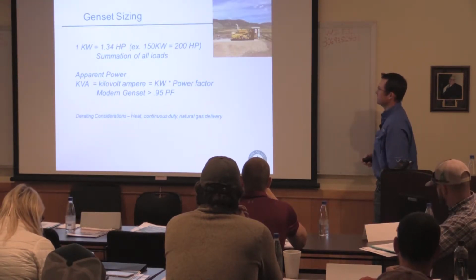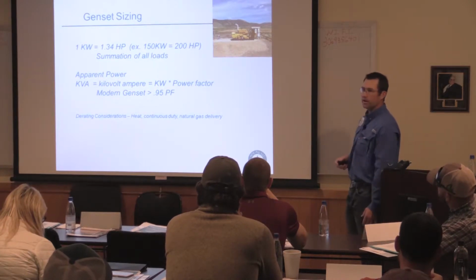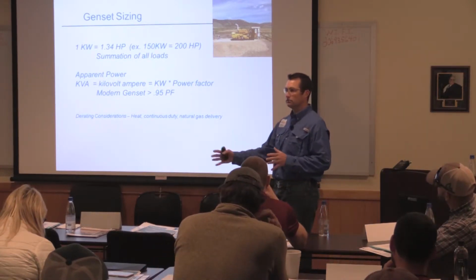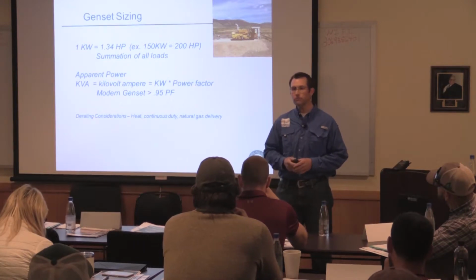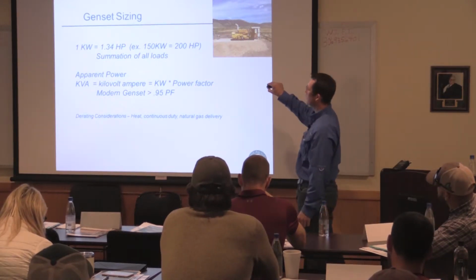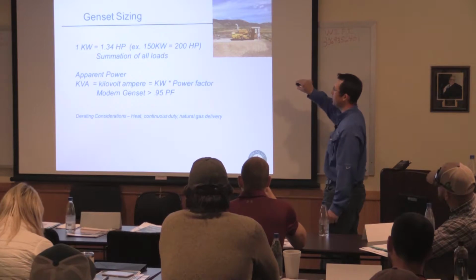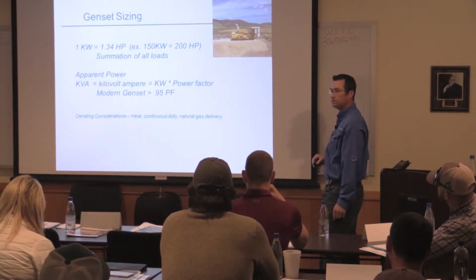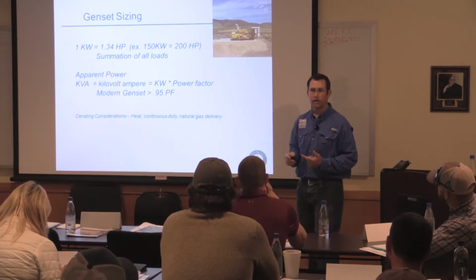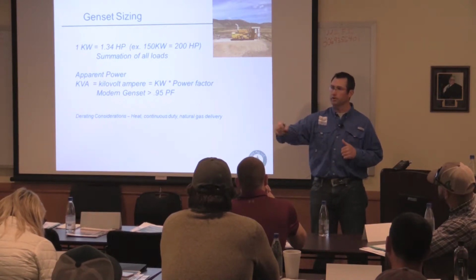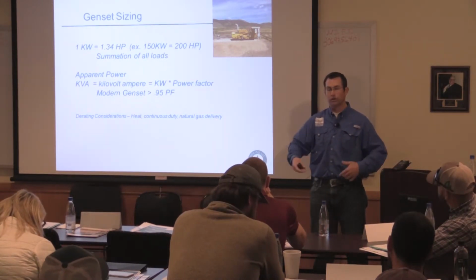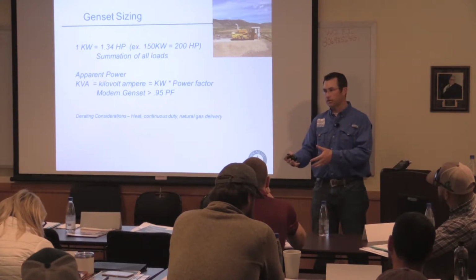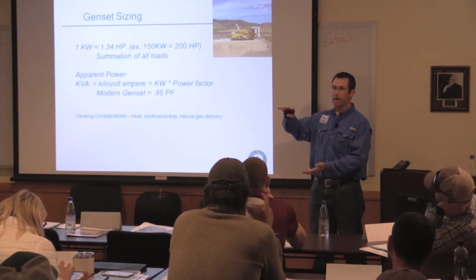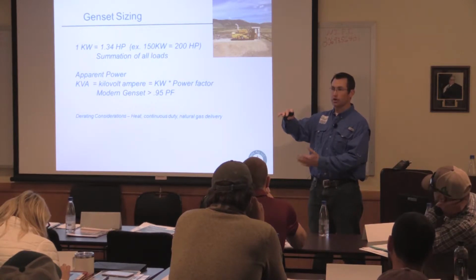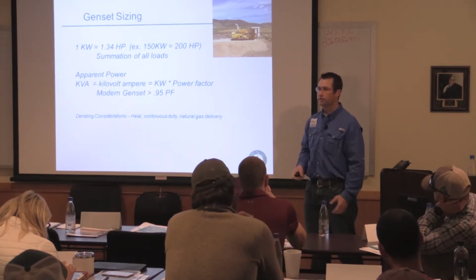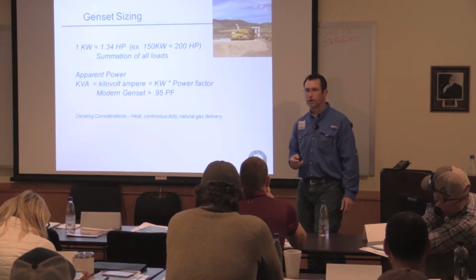Okay, so genset sizing. Here's a couple of numbers and some considerations to have. Every one of these scenarios is unique. You have to look at the summation of all of your loads that you want to put on this genset. So if you're thinking of 4 wells, you need to know what your loading is on all 4 of those wells. If you're looking at running wire to those wells, you need to look at your line loss across that wire. If you're looking at running pivots off that, you've got to add the pivots onto that. All of those accumulate to how much power you have to generate. And in some cases, you're going to run into a limit. You may need to have multiple generators if you've got a big enough system that you're trying to operate on.